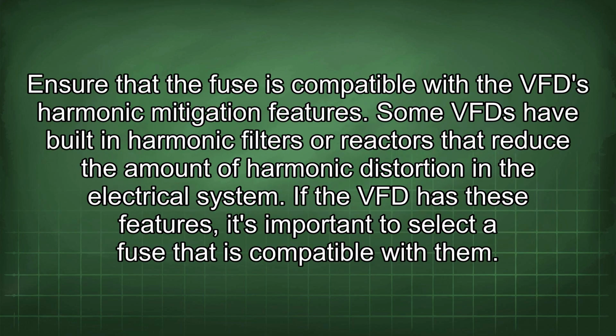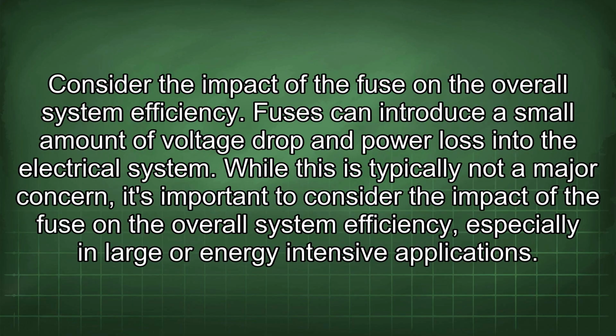Ensure that the fuse is compatible with the VFD harmonic mitigation features. Some VFDs have built-in harmonic filters or reactors that reduce the amount of harmonic distortion in the electrical system. If the VFD has these features, it's important to select a fuse that is compatible with them. Consider the impact of the fuse on the overall system efficiency.